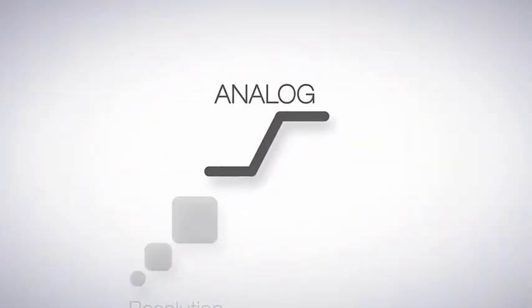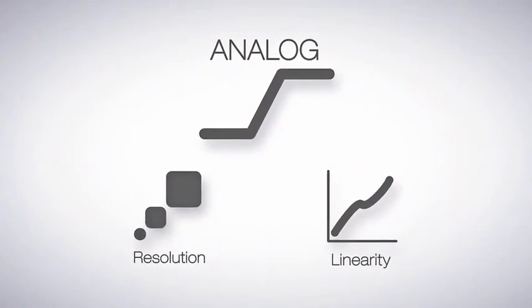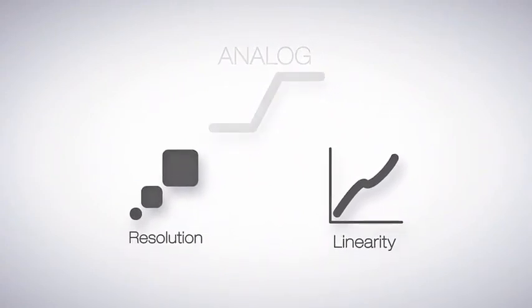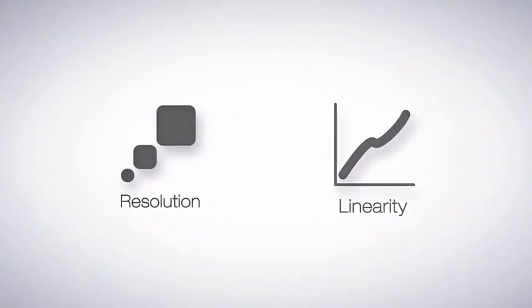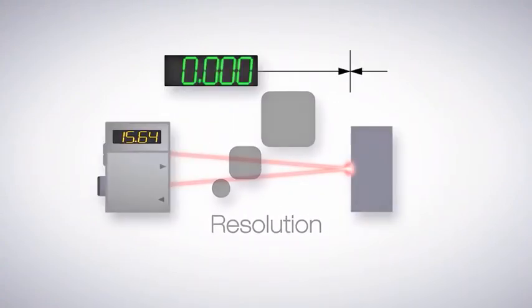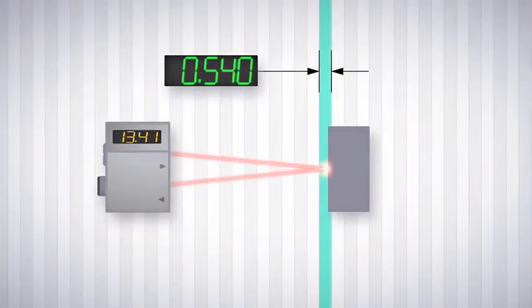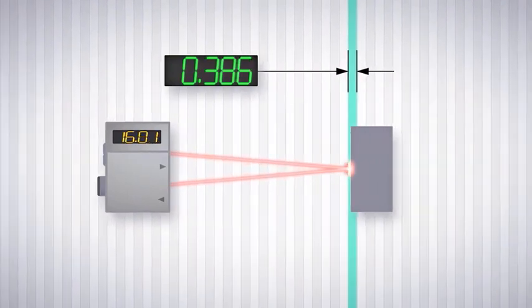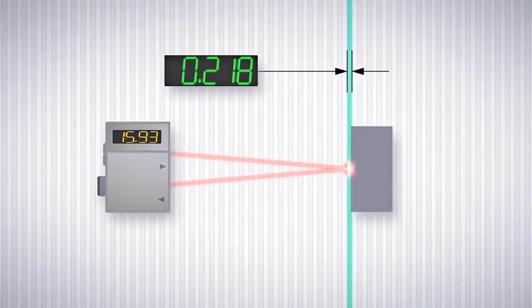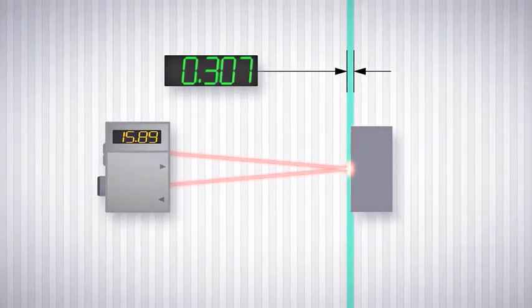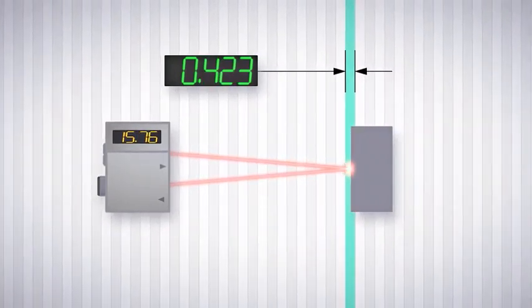In analog applications, resolution and linearity are two specifications used to describe sensors, but not all specifications are equal indicators of real-world performance. The resolution of a sensor tells you the smallest change in distance that the sensor can detect. Resolution represents the best-case condition, but it can be impacted by target conditions, distance to the target, sensor response speed, and other factors. For that reason, it is not the best indicator of real-world performance.